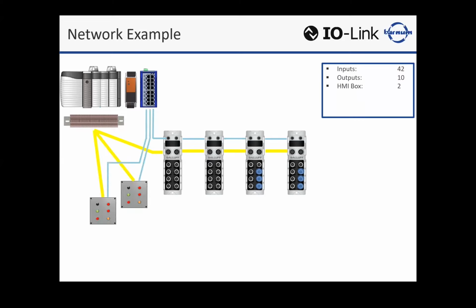For our two HMI boxes, we'll network connect those. Those have a little bit different convention. They're not just IO blocks. What we're showing for our inputs and outputs in the field is an IP67 quick M12 connector device. Typically those HMI boxes, if they're brought on the network, are using a remote IO style system where you have a communication bus head, and then you'll have slice and block IO elements that snap to that for the various inputs, outputs, analog signals. But with doing that, just like any Ethernet device, in this case we put out there, we're adding cost, because every time we need to establish communication back to the PLC via our network media, that means it's Ethernet communication. So all of those devices, we're paying for an Ethernet IP chipset, which raises the cost of our hardware.